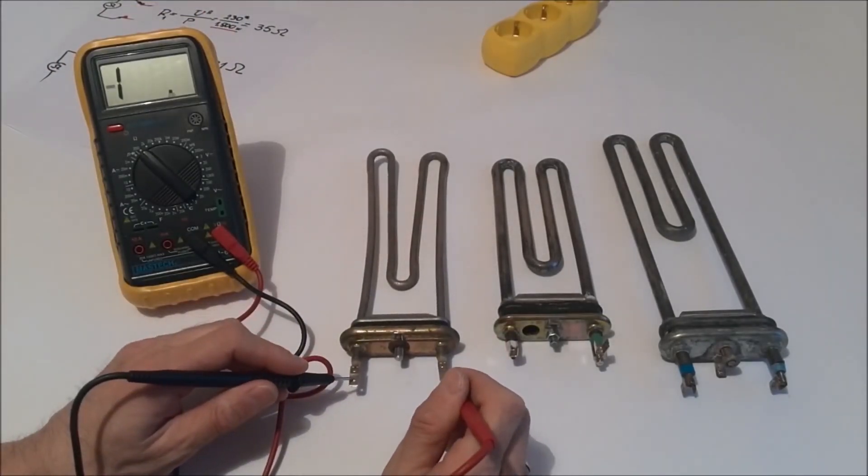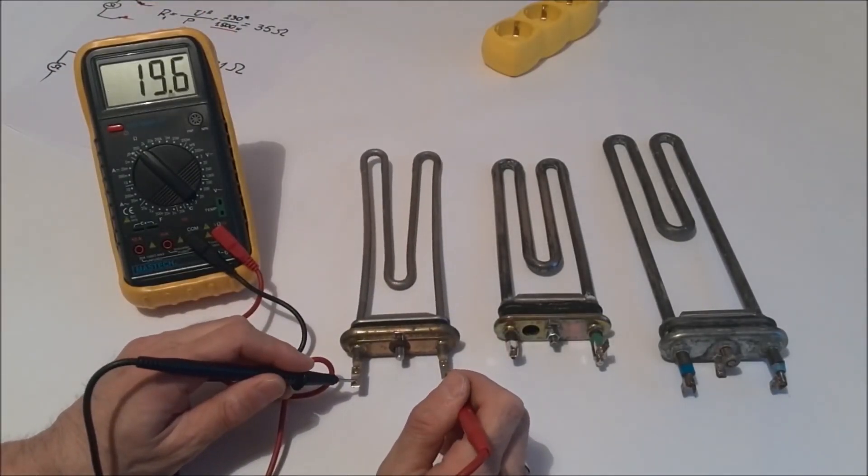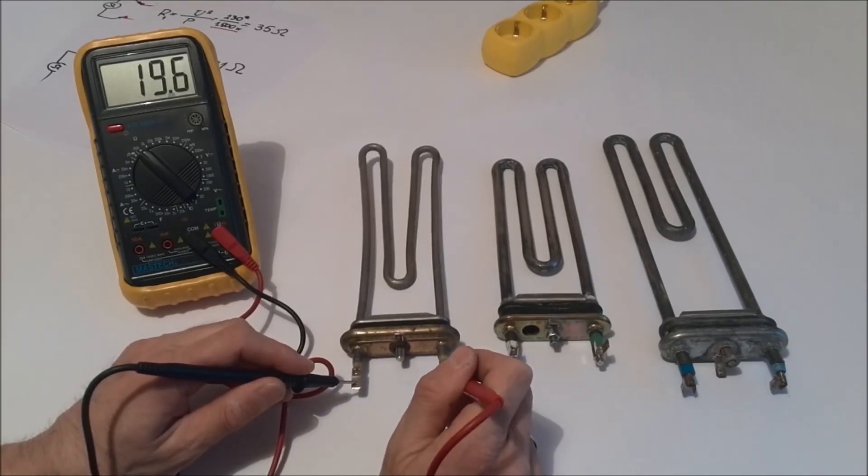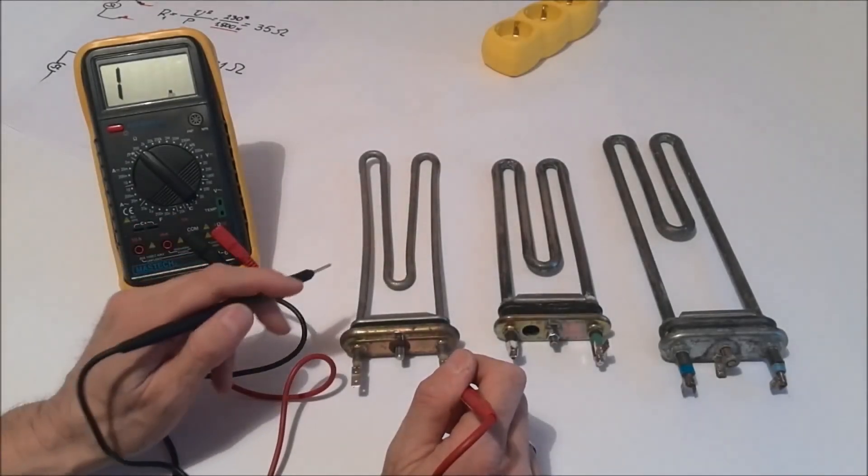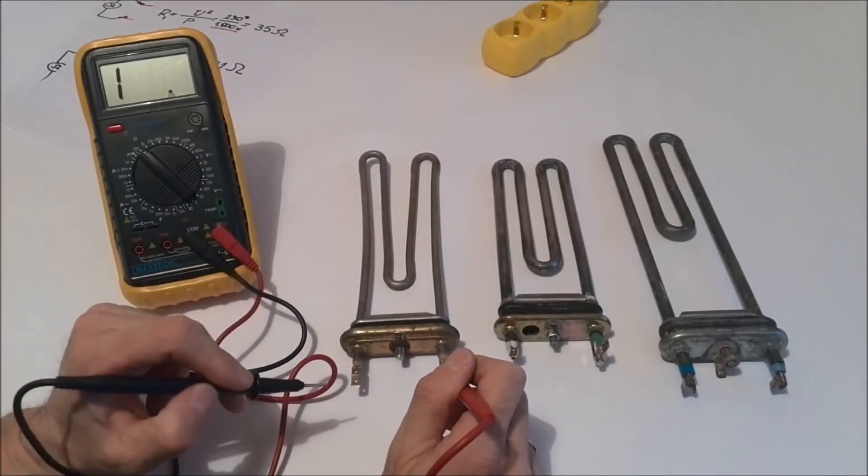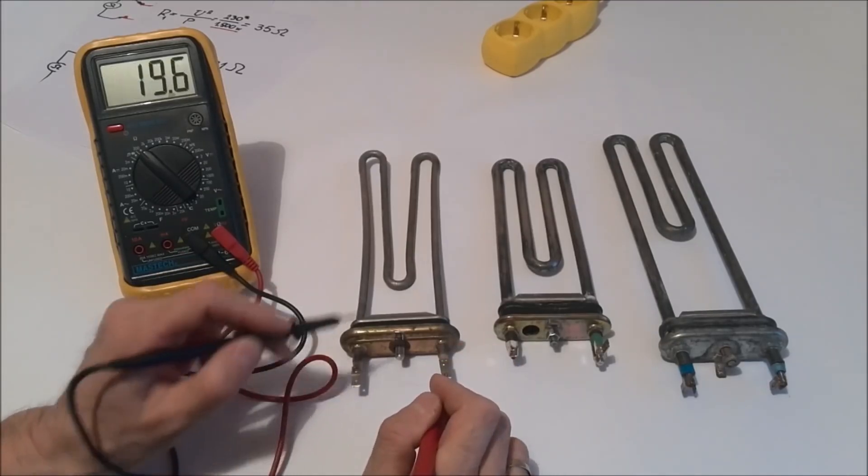We will measure the resistance of the first heater. It shows 19.6 ohms. This indicates that the heater has a chance to be working properly. We still need to check that it isn't in contact with the metal part of the cover, as workers say breaking through the mass.